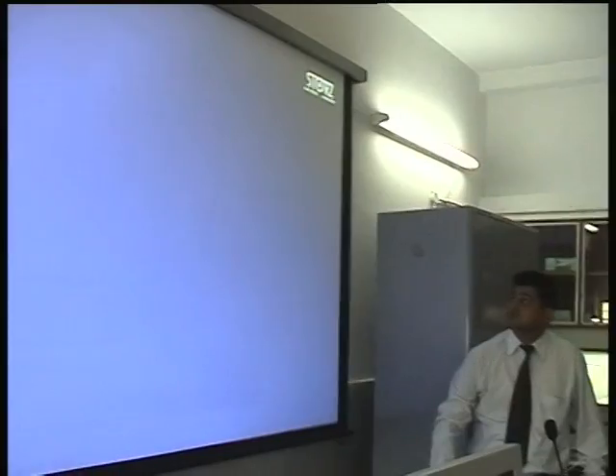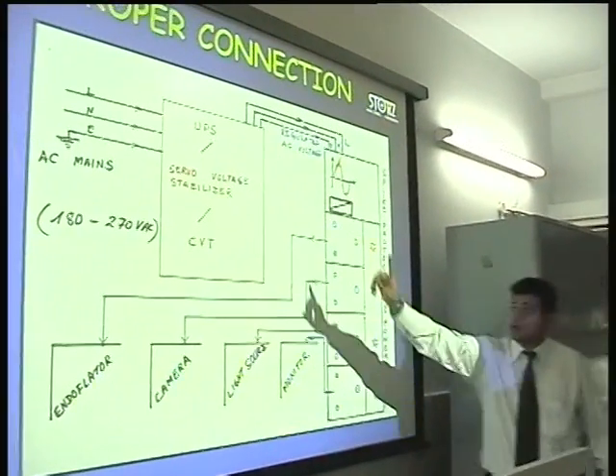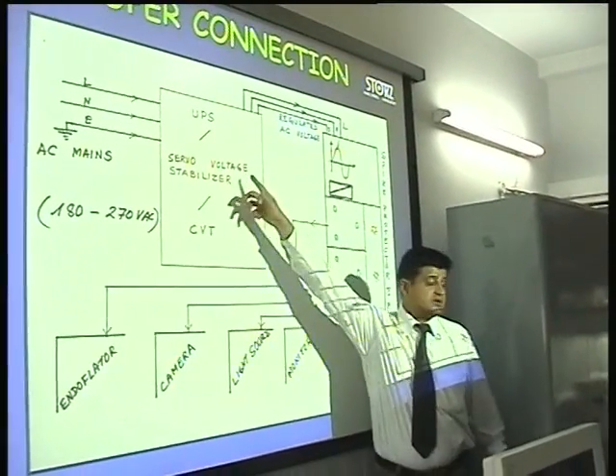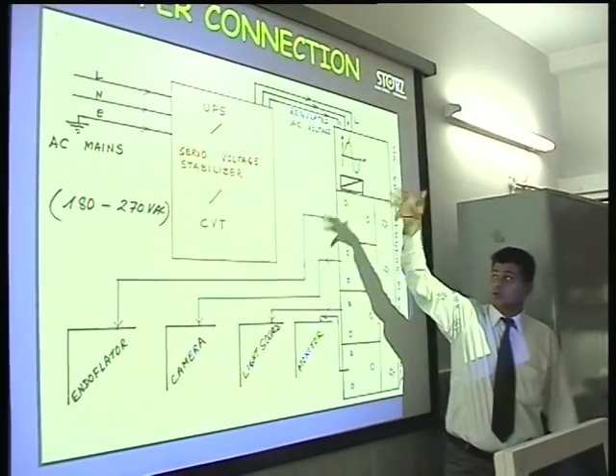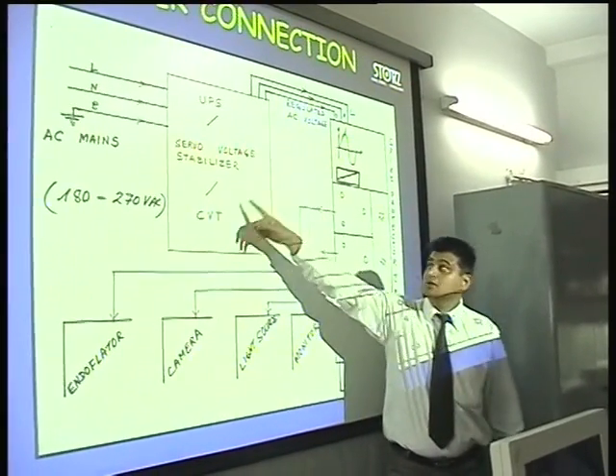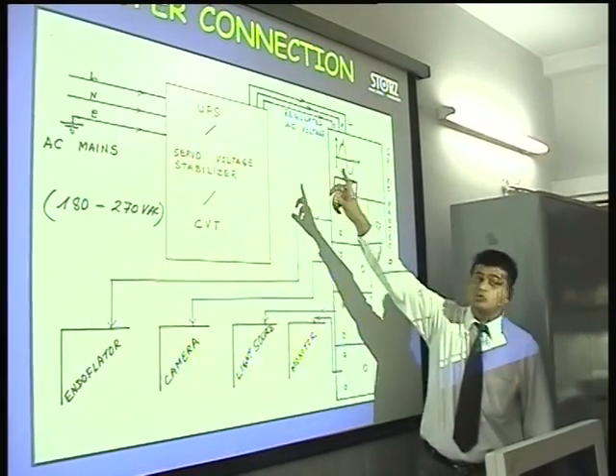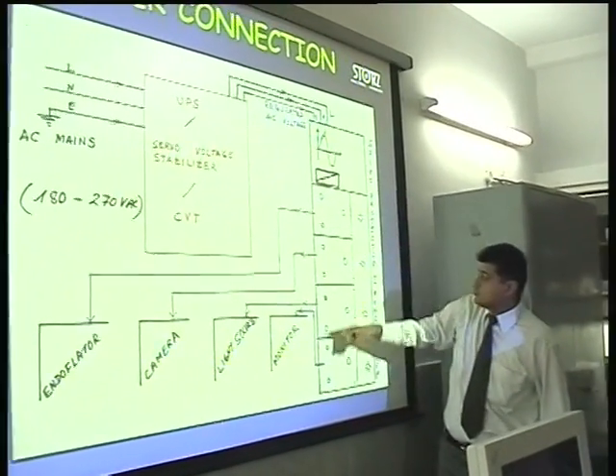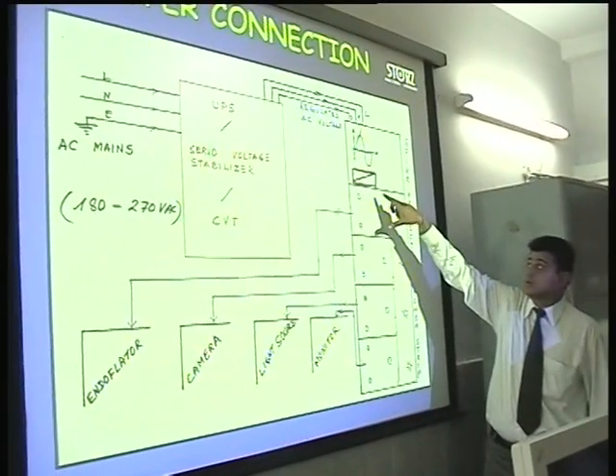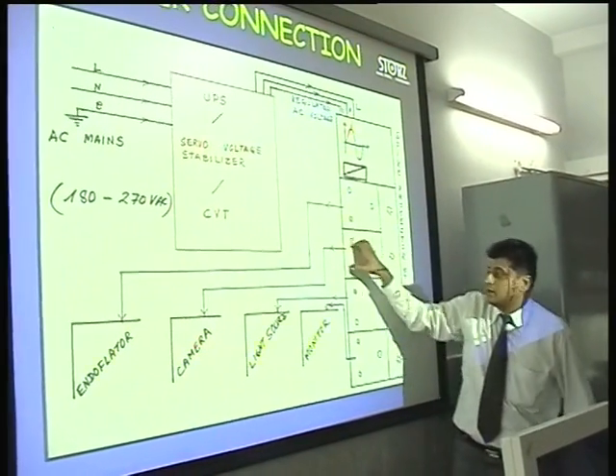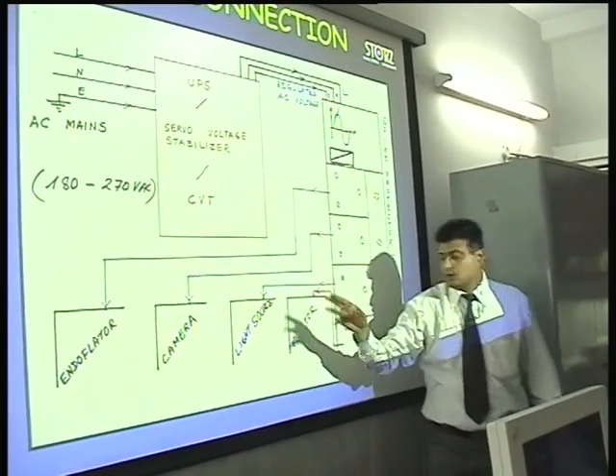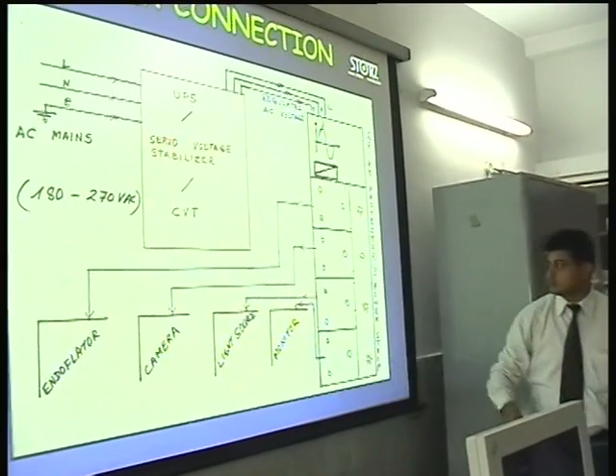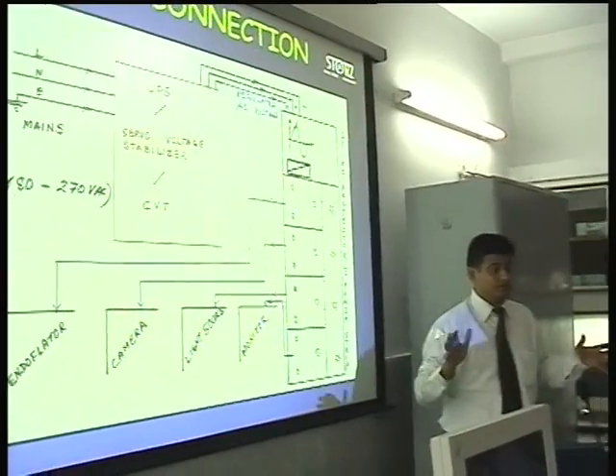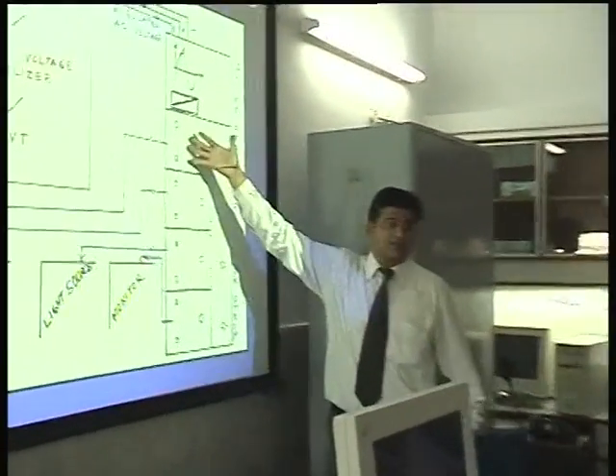Once we have a UPS, I'll show you the connection from the main ACs. We take a UPS, the best being a UPS online, but you can use a UPS offline, or you can use a CVT. So it comes through the UPS. From the UPS output, we connect a spike protector or spike surge suppressor, and from here we start connecting the electronics, which could be a camera, a light source, or a suction irrigation apparatus. Then we are safe. These gadgets can be bought, and they are not very expensive. So this is how we do it.